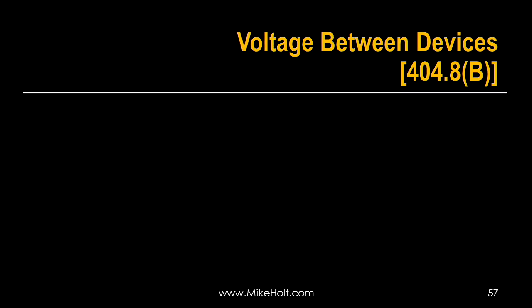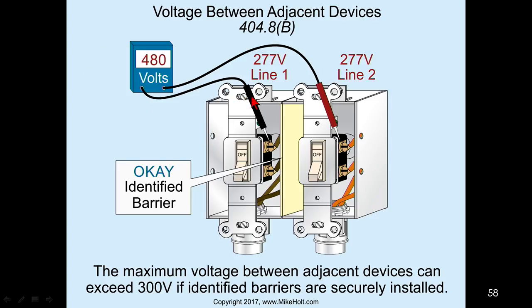Okay, let's take a look at the voltage between devices. Here we have two 277 volt switches, line 1 and line 2. The code says that the maximum voltage between adjacent devices cannot exceed 300 volts, or they can exceed 300 volts if an identified barrier is securely installed between them. So if you put a barrier here, then you can have a 277 volt switch here and a 277 volt switch here. If you didn't put the barrier, then because it's 480 volts, that would be a violation.